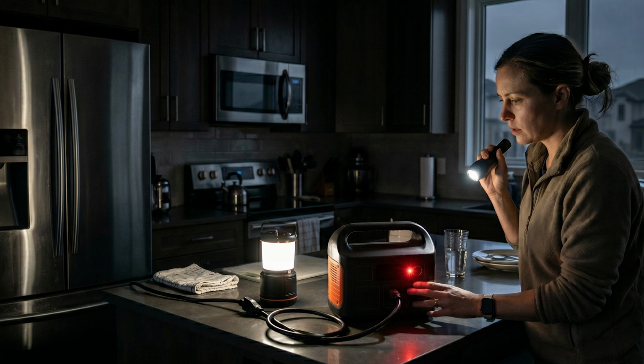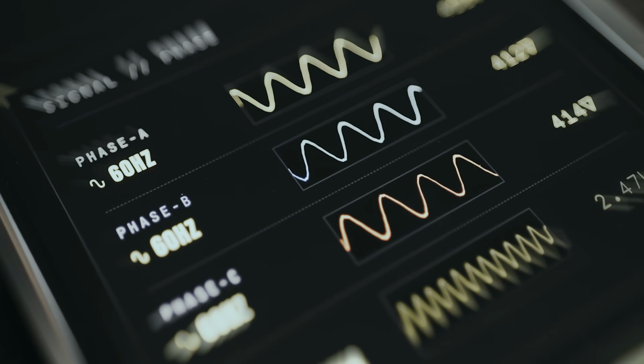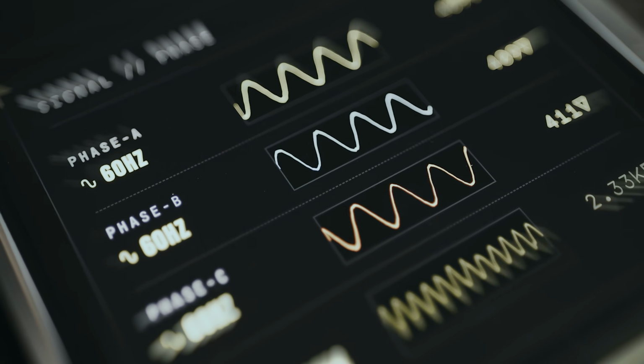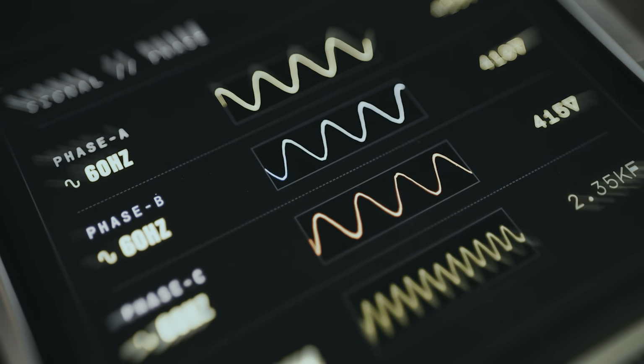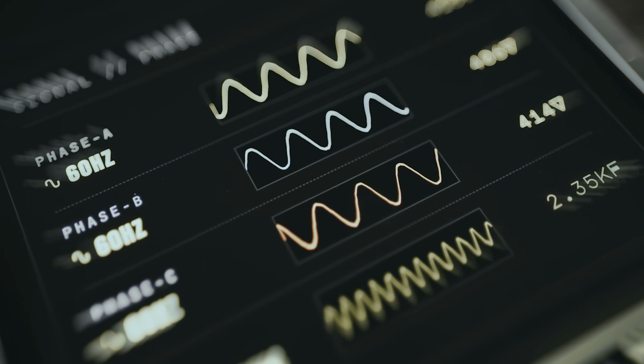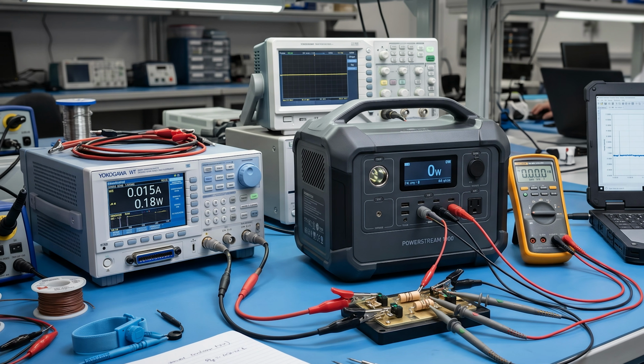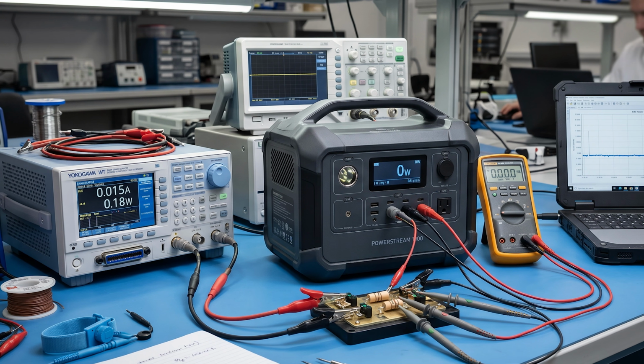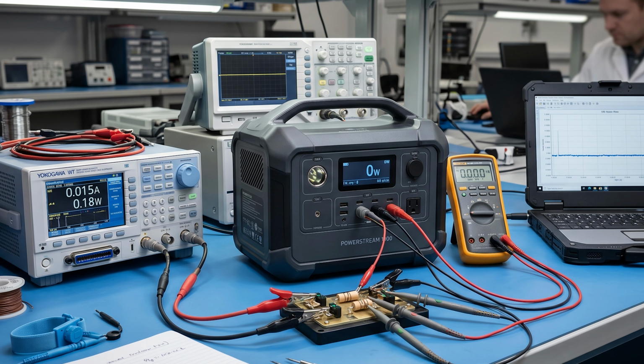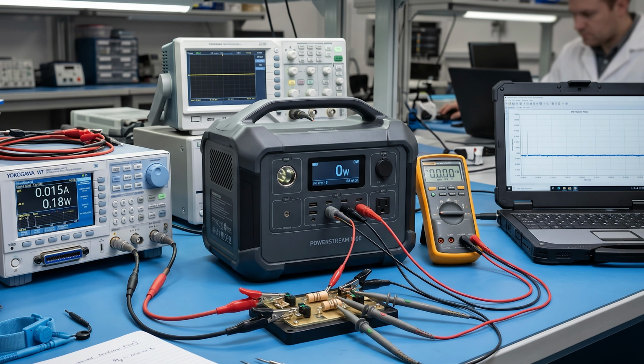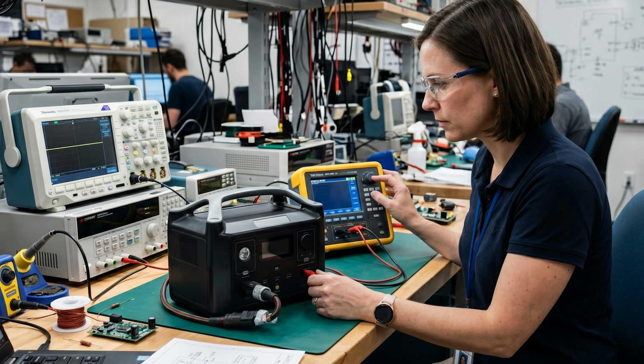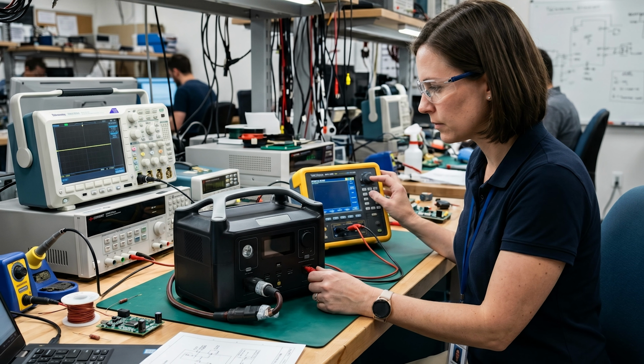When the AC inverter is switched on, the internal circuitry fully energizes whether anything is plugged in or not. The microprocessors stay active. The transformer stays fully magnetized. The switching components keep running at high frequency just to maintain a stable 120-volt sine wave, ready for an instantaneous load. That standby state draws a constant baseline from the battery.